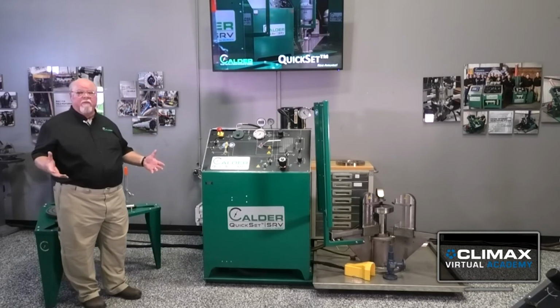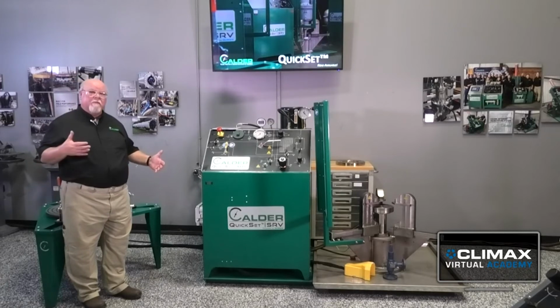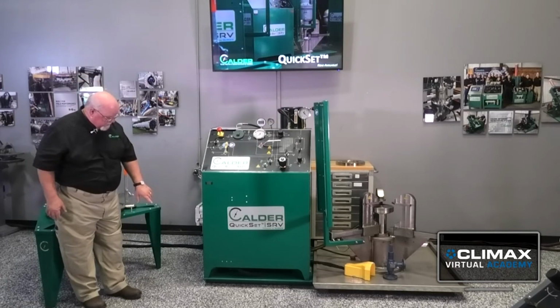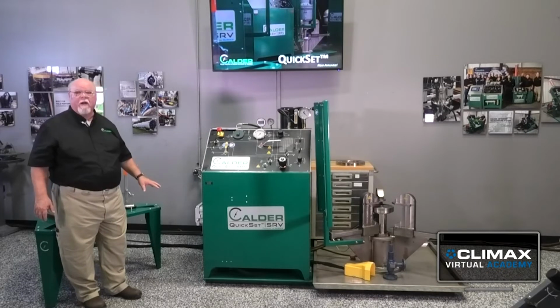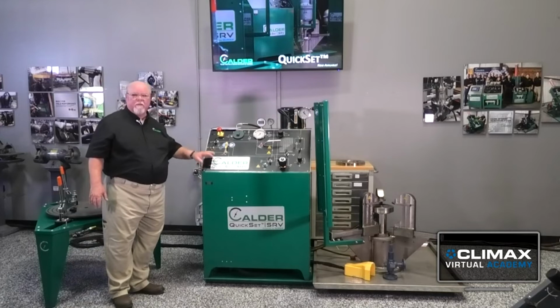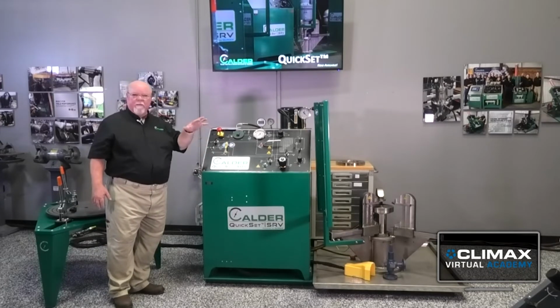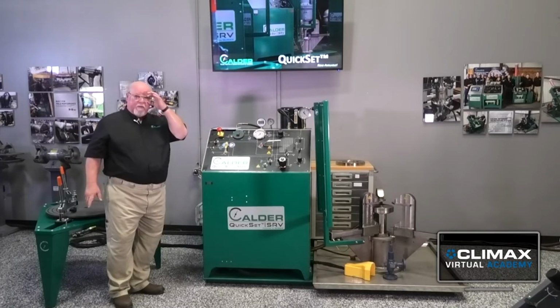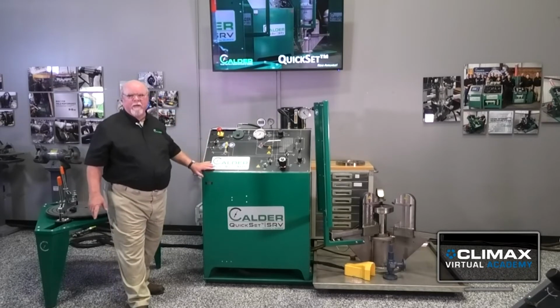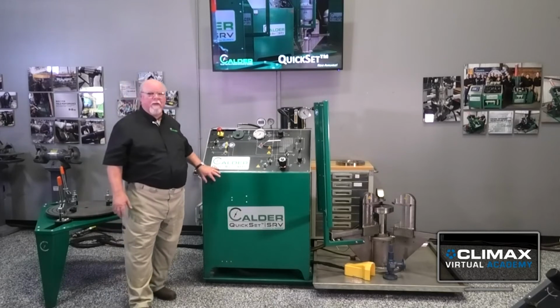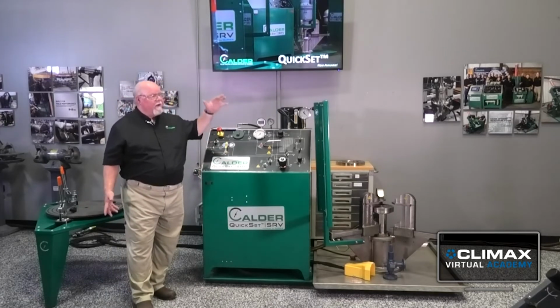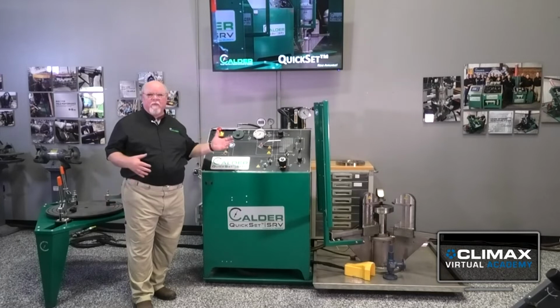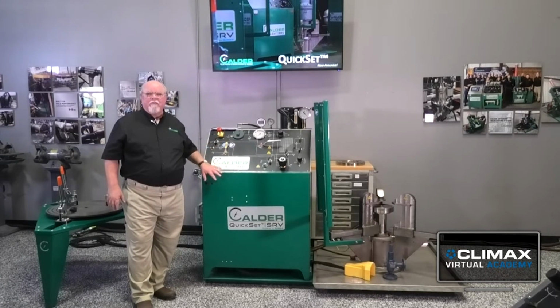Mobility. This unit is really designed to be mobile, and so if you look down on the bottom, you'll see that this is actually mounted onto a frame, and that frame is forkliftable. So it allows you to pick the complete unit up and go set it into a container, a trailer, back of a truck, whatever's needed for mobility. We do recommend you bolt it down to test, especially as the valves get bigger and bigger. The reaction force tends to be an issue, but it allows you to take it and move it from one location to another as needed.